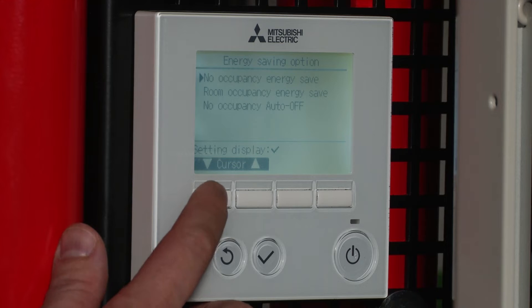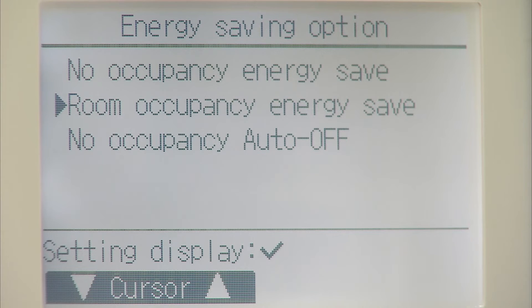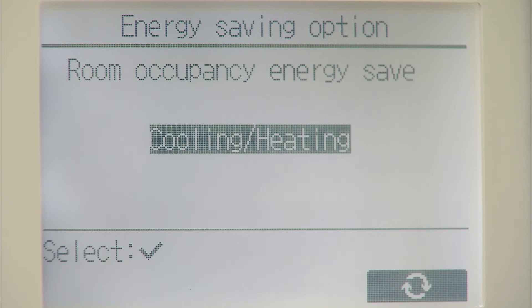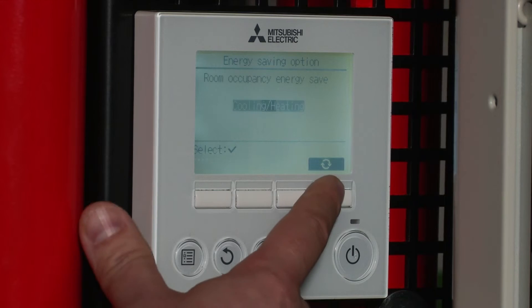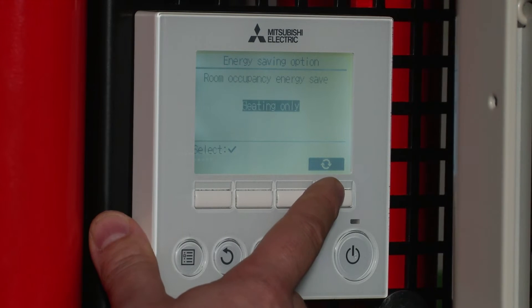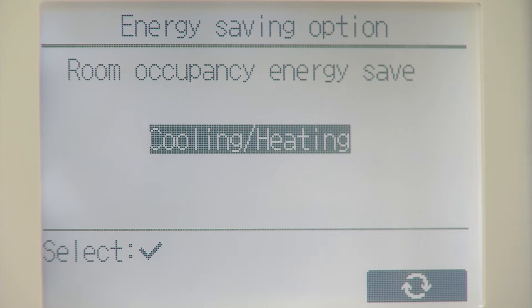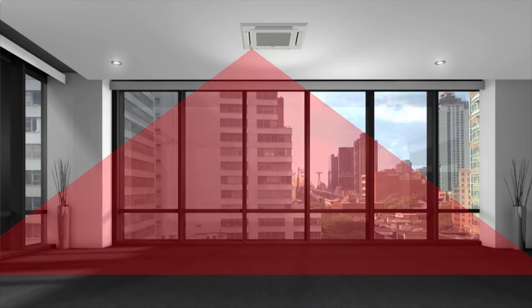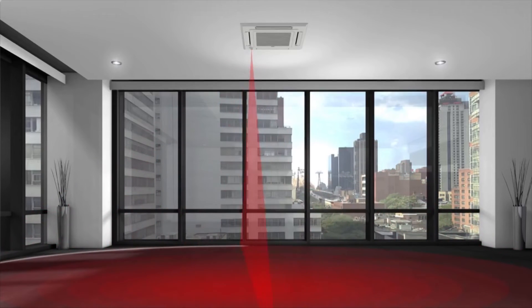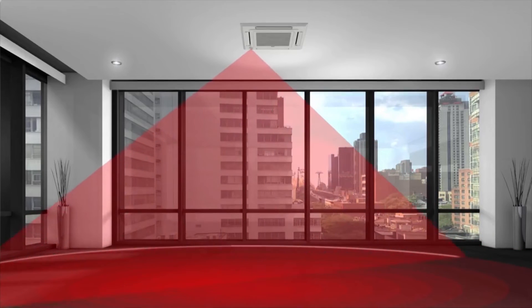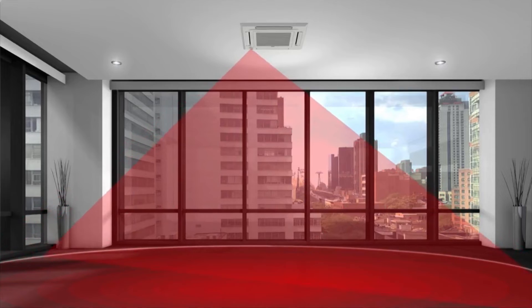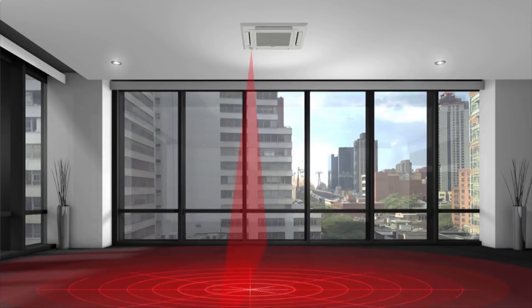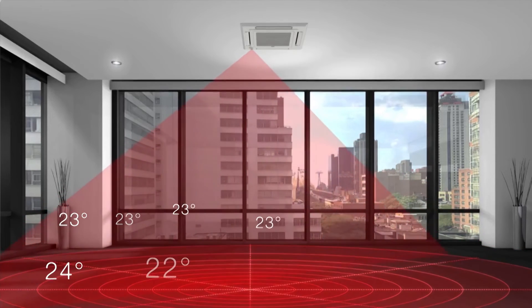If we select onto room occupancy energy saving and select on there — again, you can specify heating, cooling, or off. If we put it to heating and cooling, what the unit will now do is, if the room sees less than 30% occupancy when it does a sweep, it will drop the offset temperature by one degree. As occupancy increases, it will bring it back to the actual set temperature. This is good for examples such as bars and restaurants, where occupancy changes quite a lot.